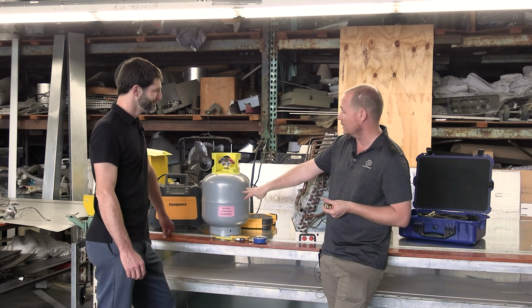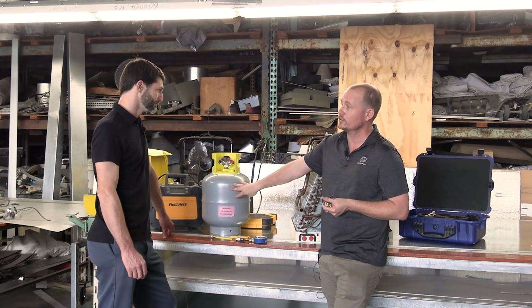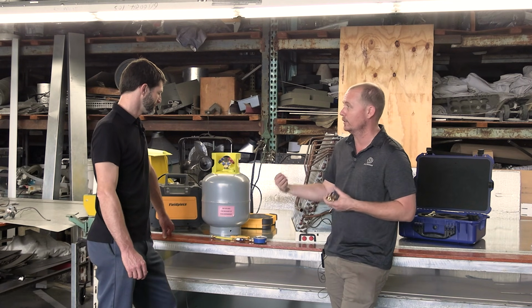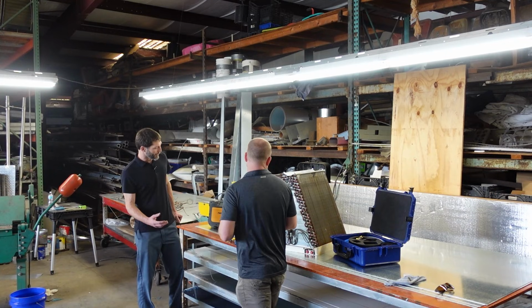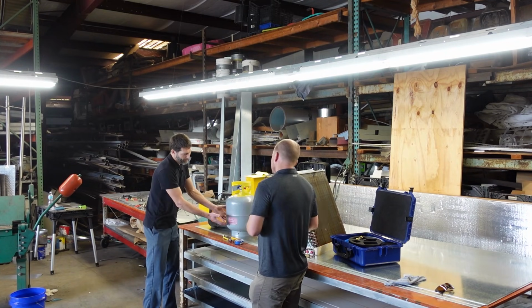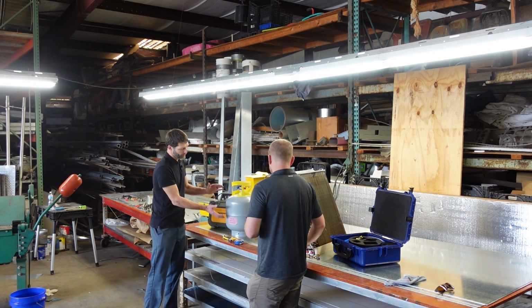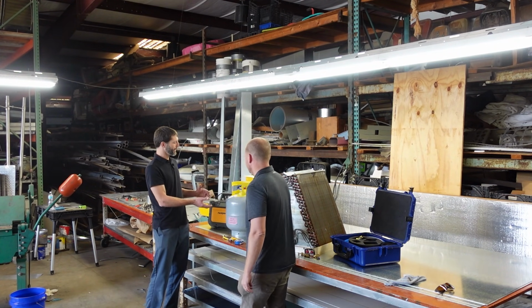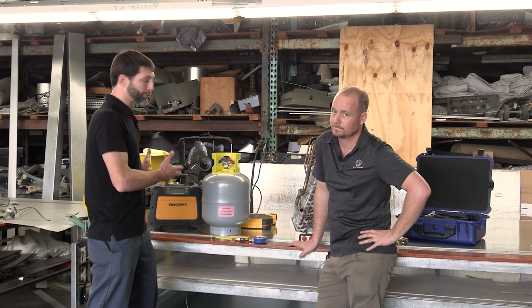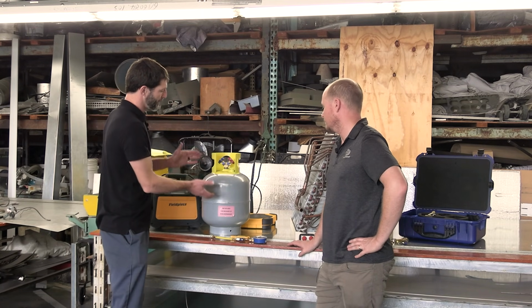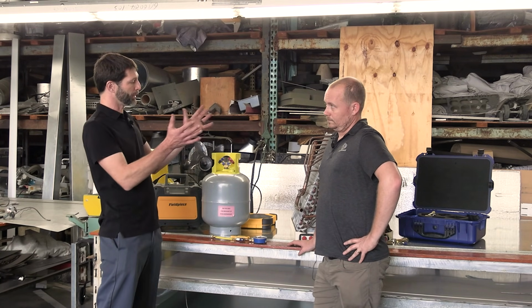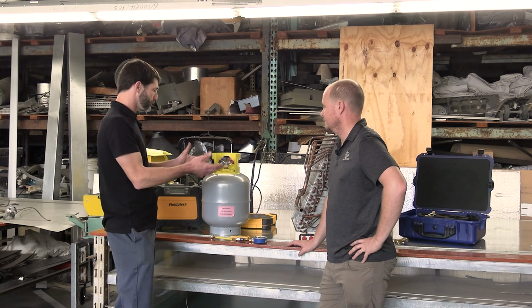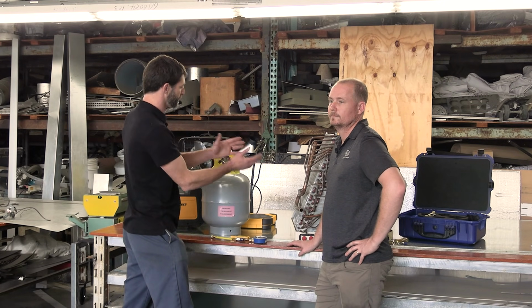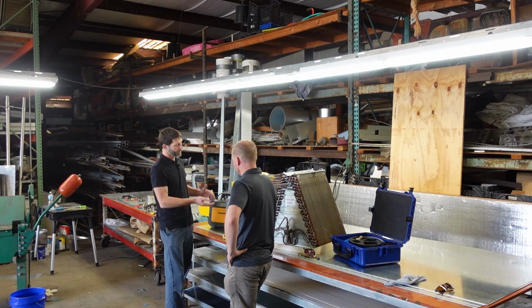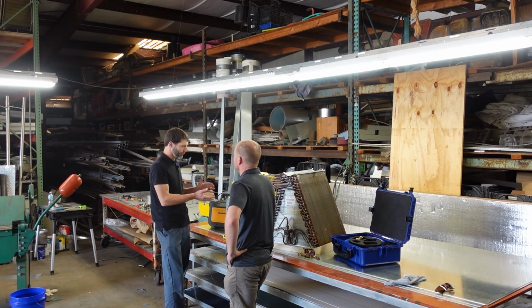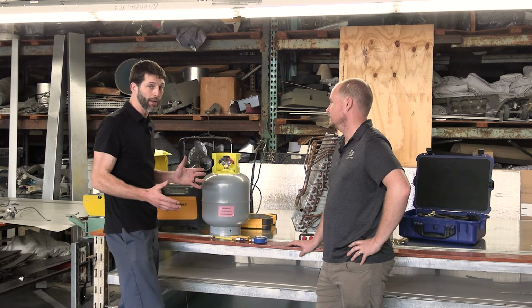But then also, let's talk a little bit about keeping the pressure low in the tank as much as possible to also speed up that process. So what you can do is put this in maybe an ice bath, something to lower the temperature of the bottle, and you could even do that without a recovery machine if the tank is at a lower temperature than the temperature of the unit. Refrigerant is going to be going from the higher pressurized area to the lower pressurized area, and so you could recover partial of the refrigerant right into the tank that way.